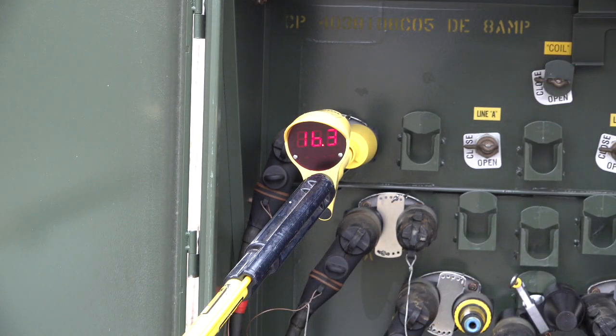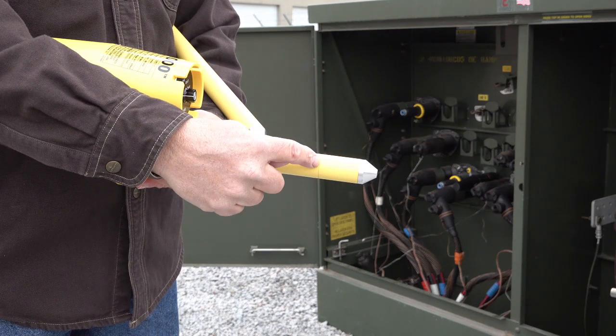So in this example, what is something that we can do to help improve the reading? On every voltage detector manufactured by Bierer Associates, we've inscribed what we call a physical limit mark. The physical limit mark is intended to give the user a visual indication. The indication is for two reasons. Number one, it alerts the user to not bypass the high voltage resistor located in the probe. And number two, if the user exceeds this limit into a ground plane or another voltage potential other than what's being tested, the meter may display incorrect readings.